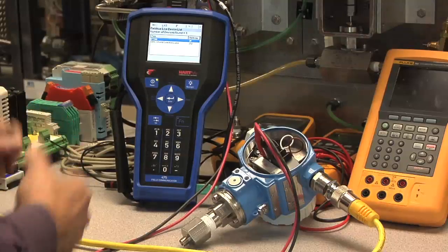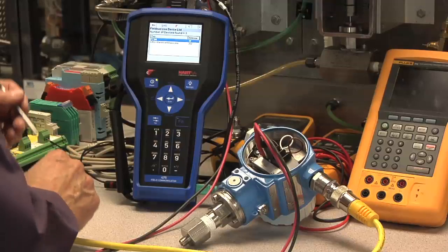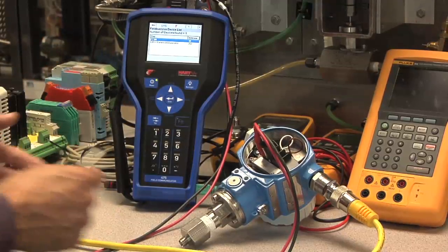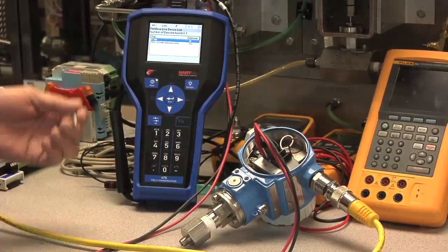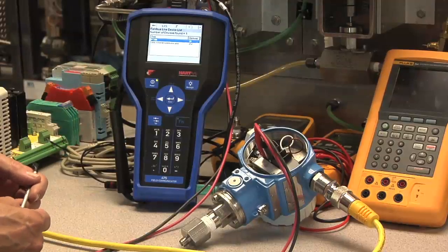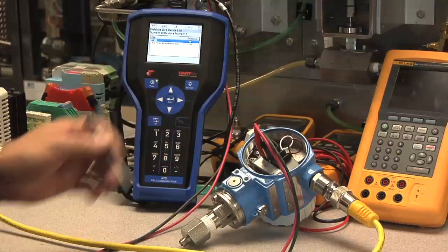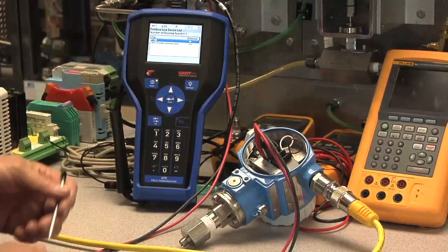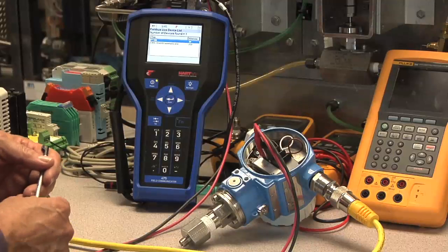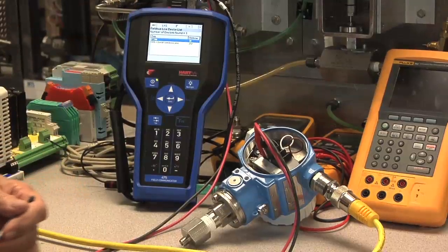So what we've done now is we've taken the transmitter, we've put it on a test bench, and basically have hooked it up with a handheld communicator, and we're hooked up to an independent segment which has no LAS on it. So the communicator is now acting as a host and has become an LAS and has gone out and located this device. The device is labeled PT100. As I mentioned, the manufacturer was asked to pre-tag the devices. So there's PT100, but somehow the address has become address 39.